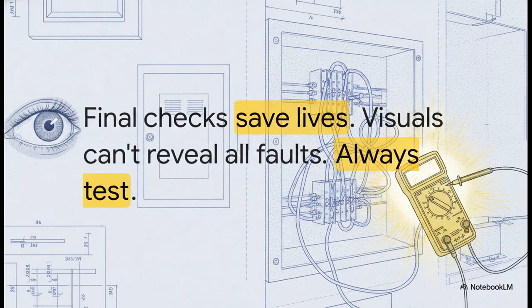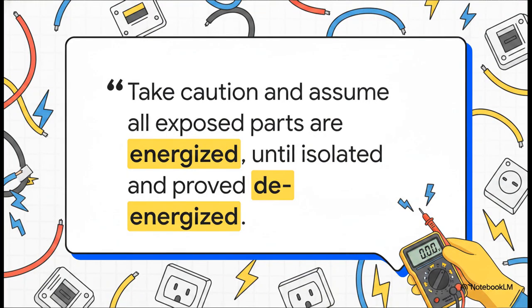What we should really take away from all this boils down to one simple, undeniable truth. In our trade, assumptions are deadly. Visual inspections are great, sure, but they can't reveal a transposed overhead line down the street or a high-impedance neutral. Rigorous, uncompromising procedural testing is literally the only way to guarantee that the installation you're walking away from is electrically safe. I want to end on this direct quote taken straight from the Safe Systems of Work. Take caution and assume all exposed parts are energized, until isolated and proved de-energized.